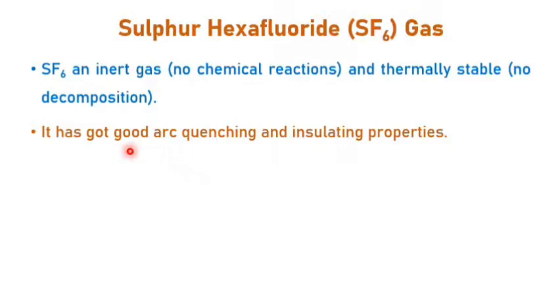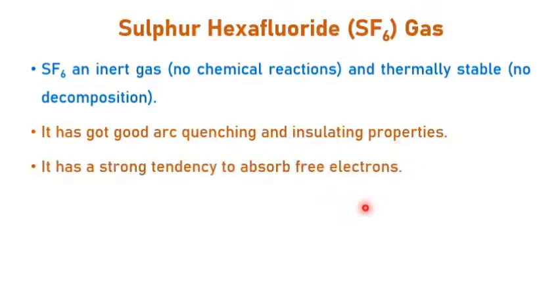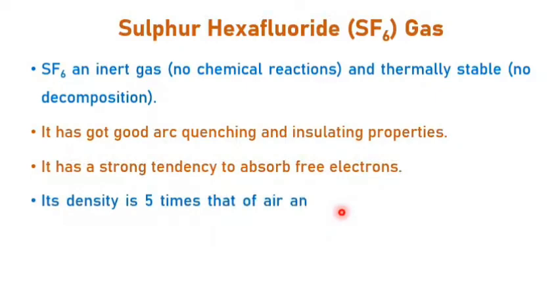And the main property of SF6 gas is it has good arc quenching and insulating properties, and it has a strong tendency to absorb free electrons. So the arc between fixed and moving contacts exists because of the ionization, or electrons present in the gap. If those electrons are absorbed, then the current cannot flow between the contacts in the air gap.